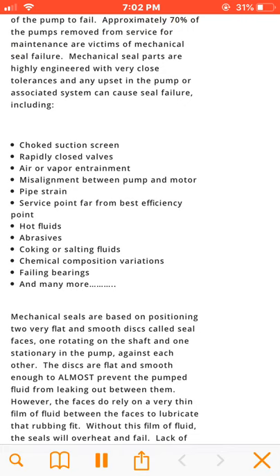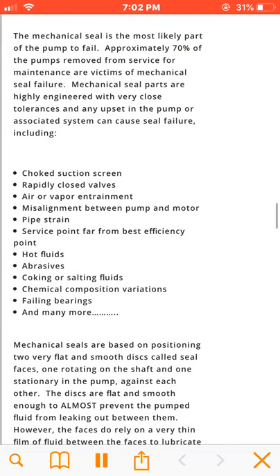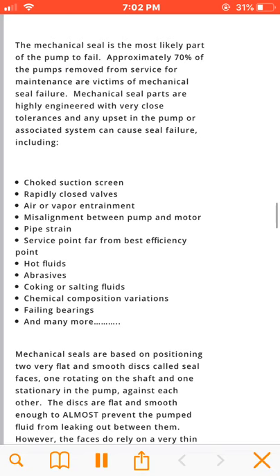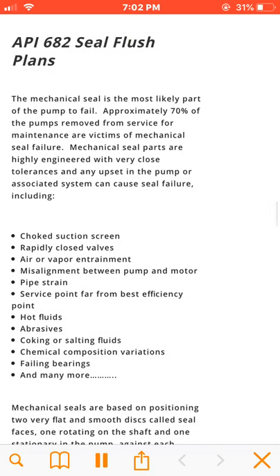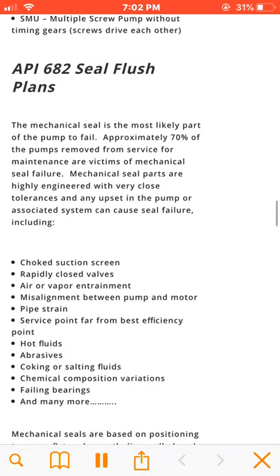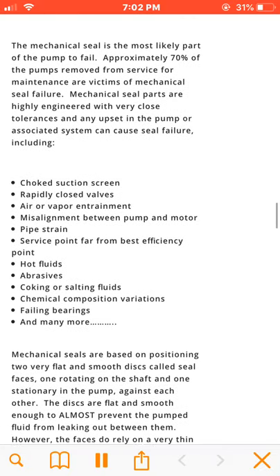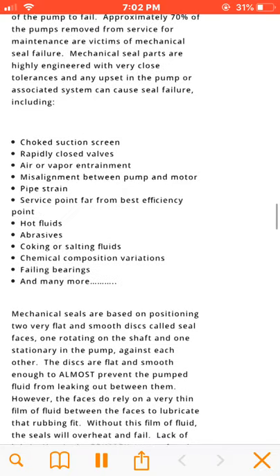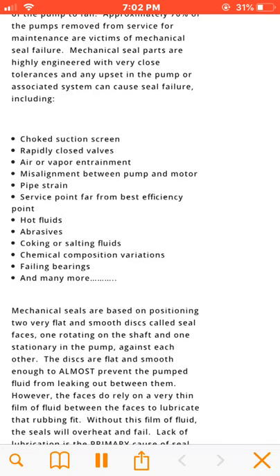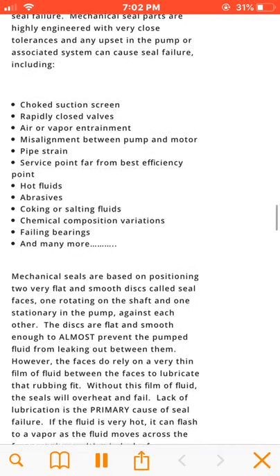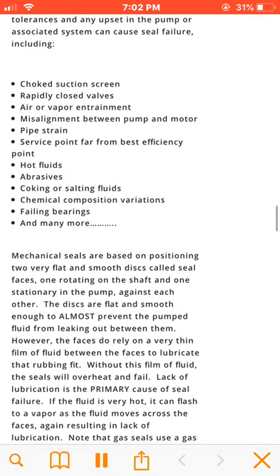Causes of mechanical seal failure include: choked suction screen, rapidly closed valves, air or vapor entrainment, misalignment between pump and motor, pipe strain, service point far from best efficiency point, hot fluids, abrasives, coking or salting fluids, chemical composition variations, failing bearings, and many more.